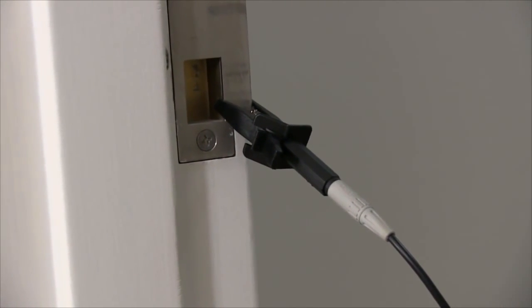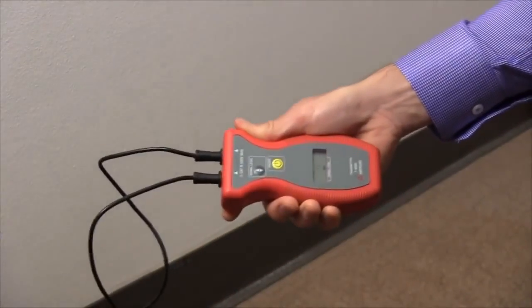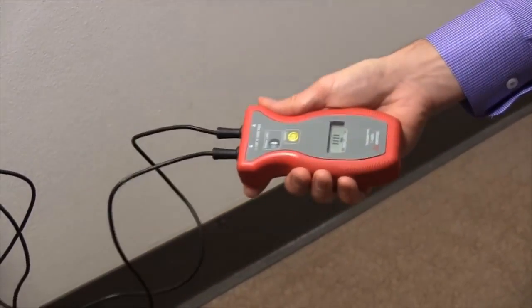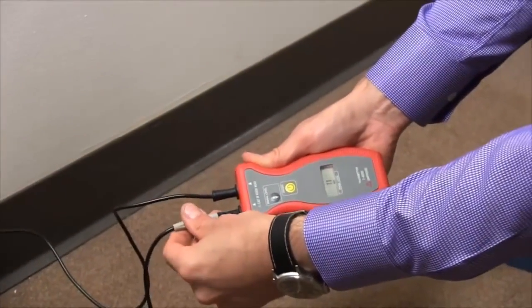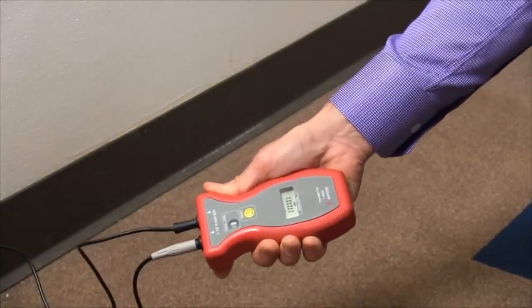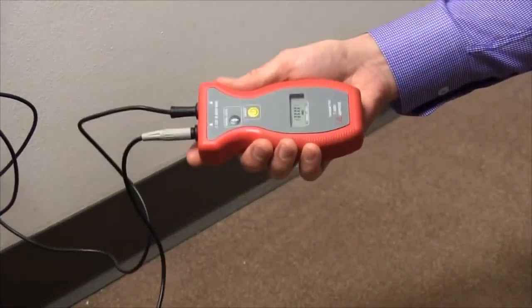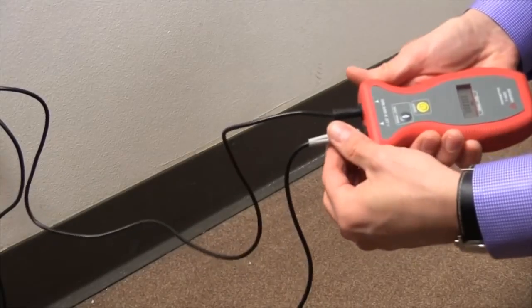You'll notice that if I plug in the other plug into the input, there's nothing. As soon as I plug the ground back into the unit, the signal returns. So again, having the transmitter grounded with only one source providing a signal is very important.